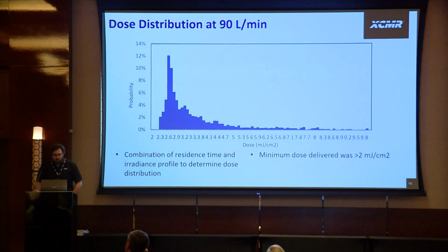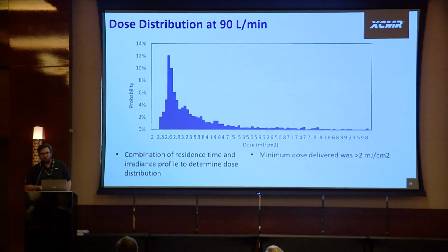With this dose distribution, if you're looking at the minimum dose, I believe that's on the order of 2 log inactivation, so about 99% inactivation. This dose does increase, and if you looked at the average dose, you would get a larger inactivation, but we were designing for the worst case scenario, so we took the lowest dose when we were evaluating different light sources and things like that.